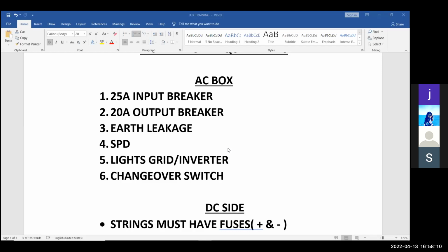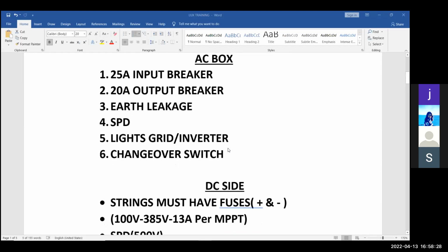So it's technically not necessary to have an SPD on the AC output of the inverter, but if you have the chance and the funds, you can add an SPD there as well. It's always safer to add SPDs on the input and the output side of the inverters if it's possible. So that's on the AC side of these inverters. So it's basically, just to recap there, a 20 amp output breaker, a 25 amp input breaker.